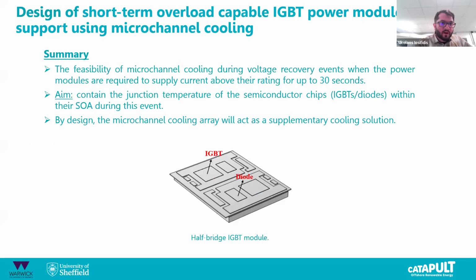So this is the bulk of the work that we have done here, and in my PhD, experimental based. It's a feasibility study of microchannel cooling during overloads for up to 30 seconds. So the aim is simple. It's just to contain the semiconductor chip temperatures within the safe operating limits. By design, this microchannel array will work as a supplementary cooling solution and not as the only one, but it's supposed to be there to give a faster cooling response to the temperature rise during the overload event. Next slide, please.